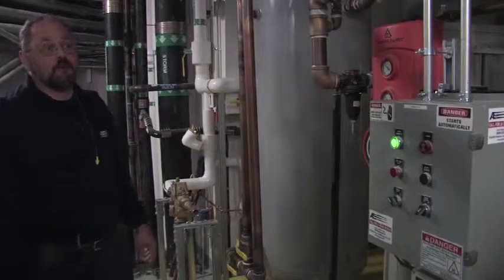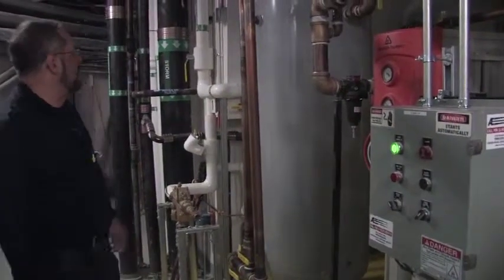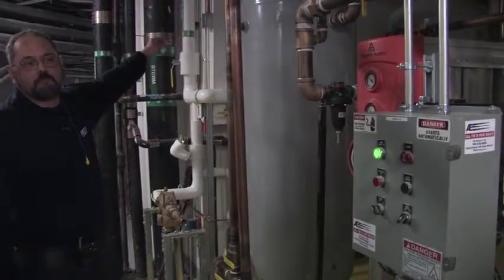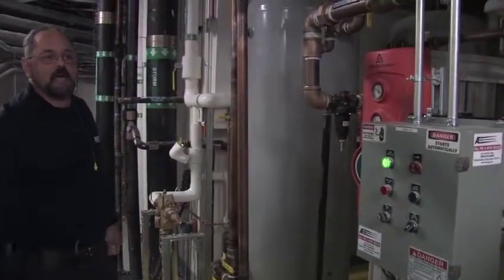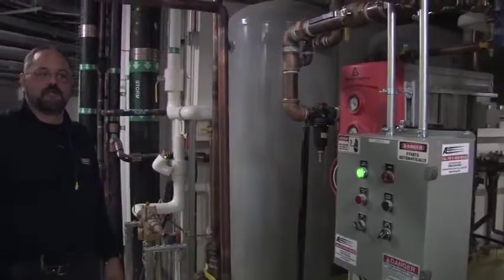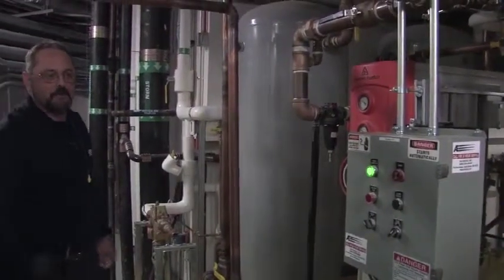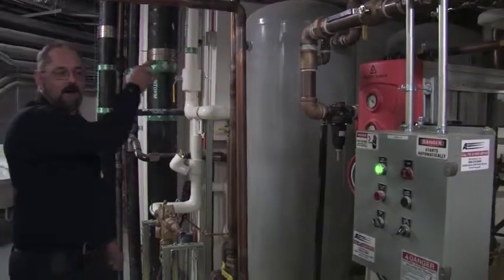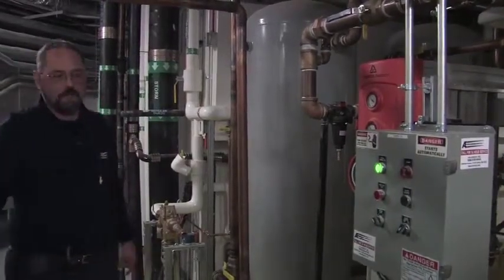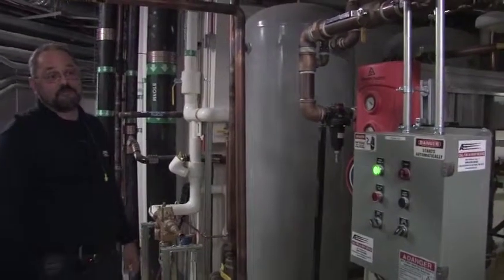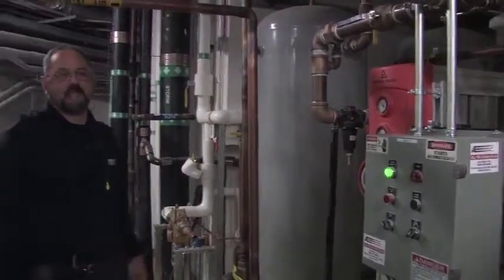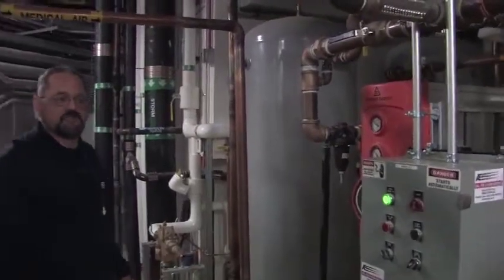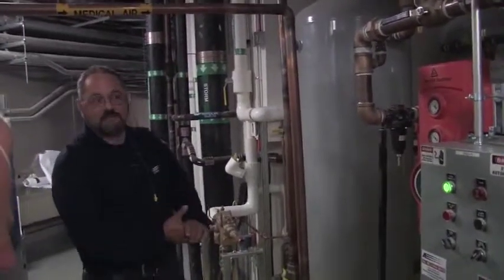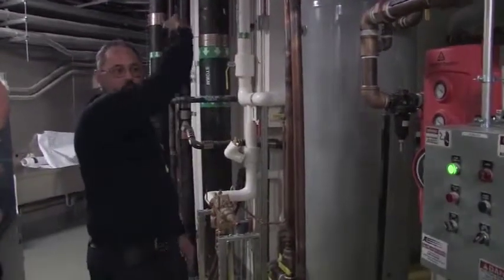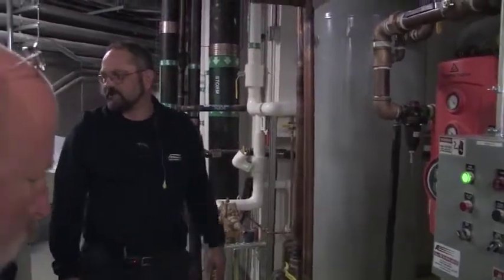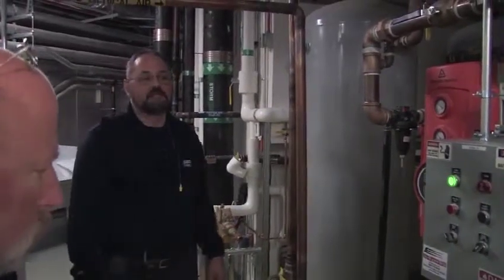They weren't getting it everywhere yet, but we were putting in a new sequencing system, and we went to a tap three-quarters of the way up the tank where there was a petcock and a gauge, and we put our new line on to run to our new transducer on the sequencing panel. And when we cracked the petcock, our new piece of tubing filled with water instantly. So we were three-quarters of the way up the side of that 24-foot tall tank. The good news is they were still 1.5 feet below the intake pipe, which would have brought the water back to the compressors and trashed the compressors. So it was kind of a good thing they had us in to do that.